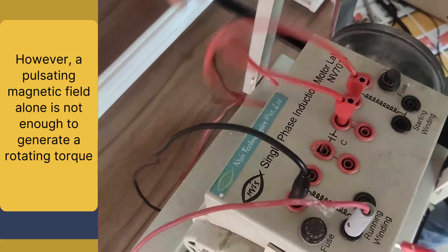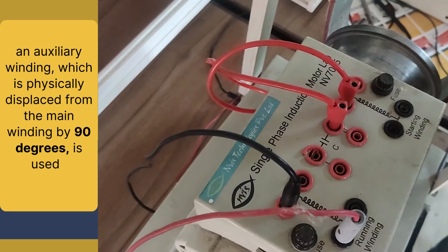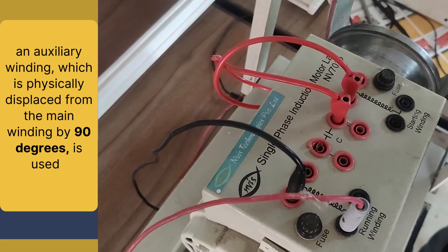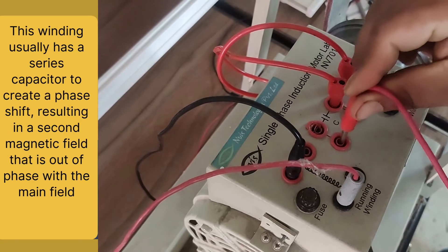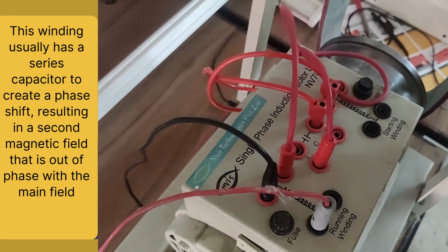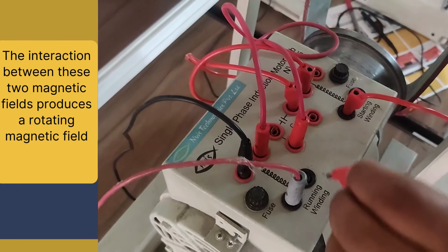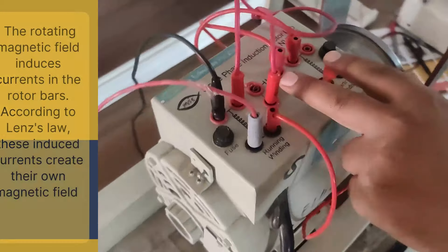So to overcome this problem, an auxiliary winding which is physically displaced from the main winding by 90 degrees is used. This winding usually has a series capacitor to create a phase shift, resulting in a second magnetic field that is out of phase with the main field. The interaction between these two magnetic fields produces a rotating magnetic field.